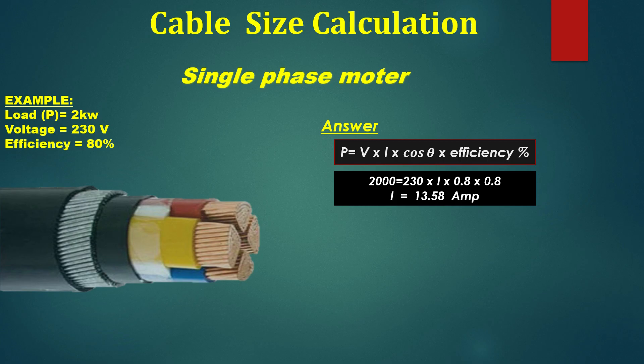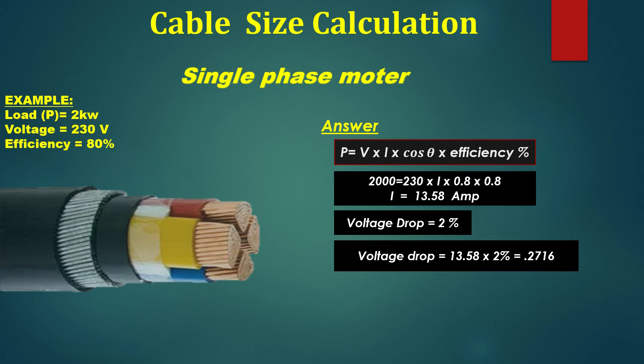Now, put the values in formula. 2000 is equal to 230 multiplied by current multiplied by 0.8 multiplied by 0.8. So, the current is 13.58 ampere. For every single phase motor have 2% voltage drop. So, voltage drop is equal to 13.58 multiplied by 2%. The answer becomes 0.2716.